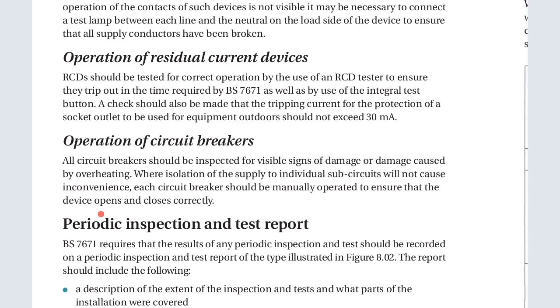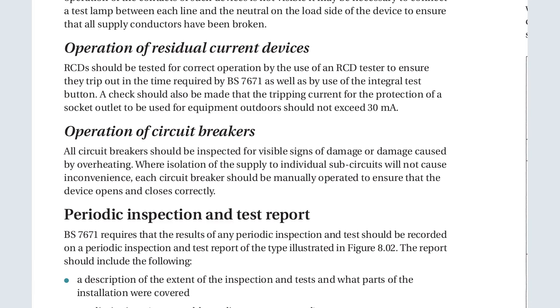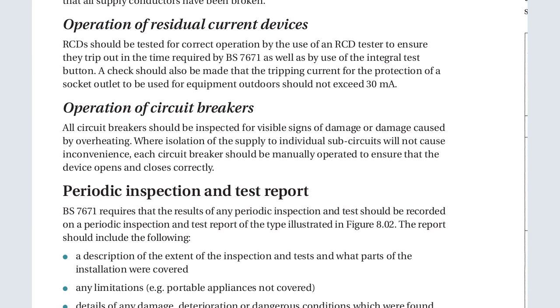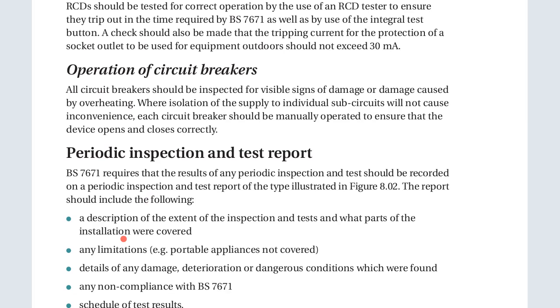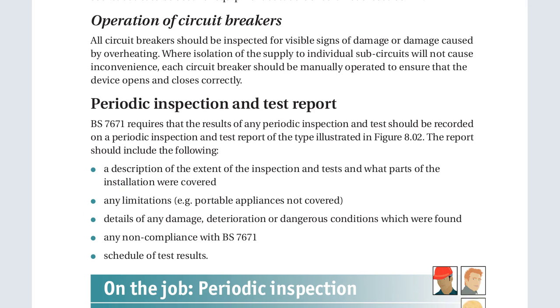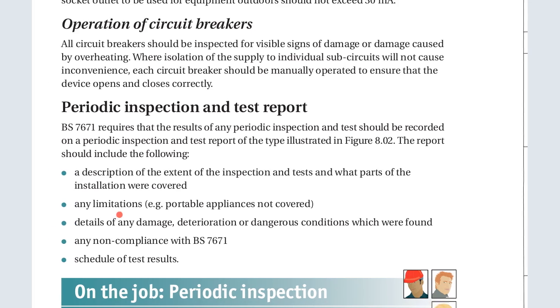Another one is the operation of the residual current devices. The RCD should be tested for correct operation by use of the RCD tester, to ensure that it trips out in the time required by the standards, as well as by use of the integral test button. A check should also be made that the tripping current of the protection of a socket outlet used for equipment outdoors does not exceed 30 milliamperes. Operation of the circuit breakers: all circuit breakers should be inspected for visible signs of damage or damage caused by overheating, where isolation of the supply to individual sub-circuits will not cause inconvenience.